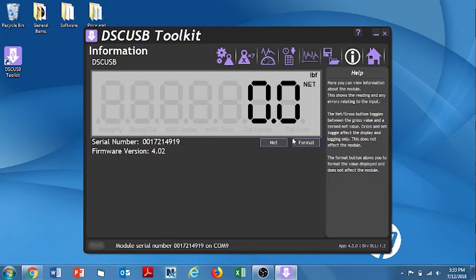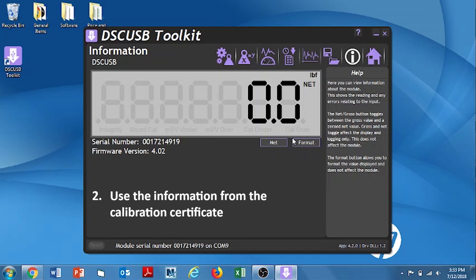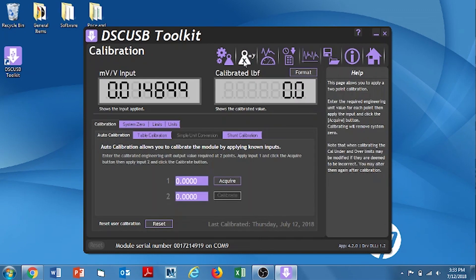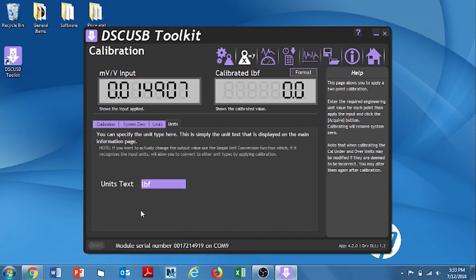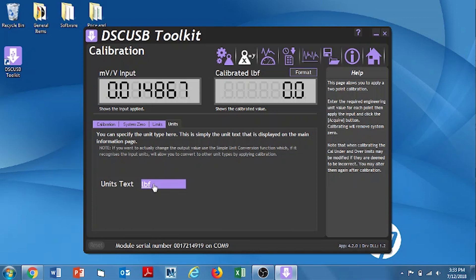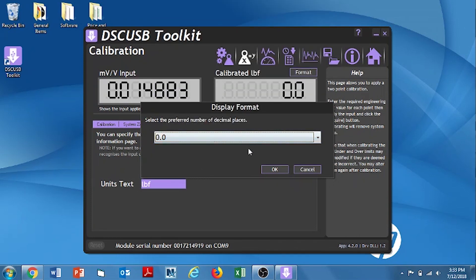Now we're going to start with calibration method number two, which is using the calibration cert that was received from interface for the load cell. First, we go to the calibration icon. And then we want to make sure that we set the unit correctly. In this case, we're going to use LBF. But if we needed a different one, we could just click on it here and type in the new unit. And then we want to set the format. In this case, we're going to use this one decimal place to the right. But if you needed other ones, you could go here and select a different one. And then click OK.